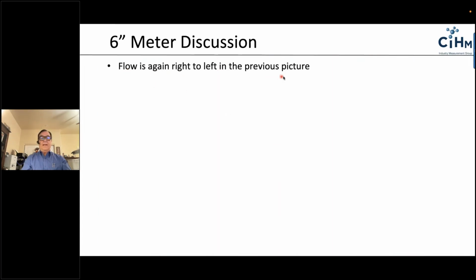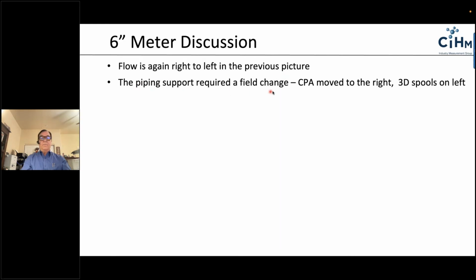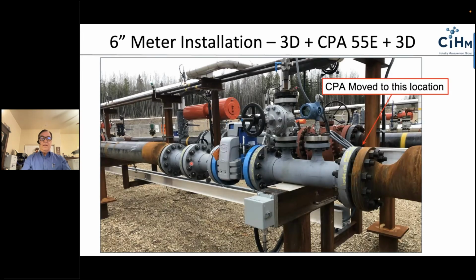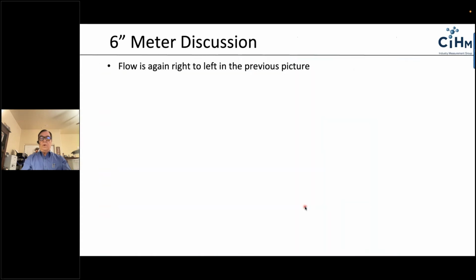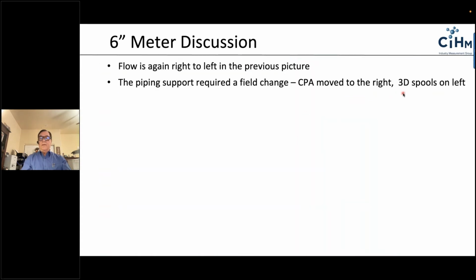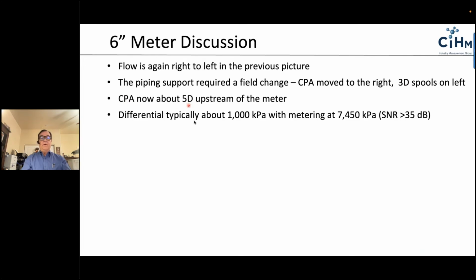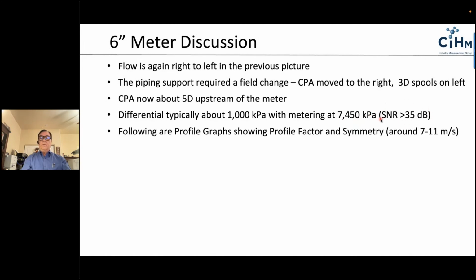So again, the flow was right to left in the previous picture. The piping support in the middle required that the CPA be moved to the right-hand side. In other words, the piping support we see right here would have been right in the middle of the flanged area, so that was not going to work. So the client, with a limited amount of time, had to move the CPA and put the spools downstream for the 3D spools. The CPA now is around 5D on the upstream of the meter. Upstream of this meter, about 1,000 kPa of differential on a regulator, and again, this meter also runs around 7,450 kPa. Signal to noise, once again, well in the strong range, up above 35 dB.